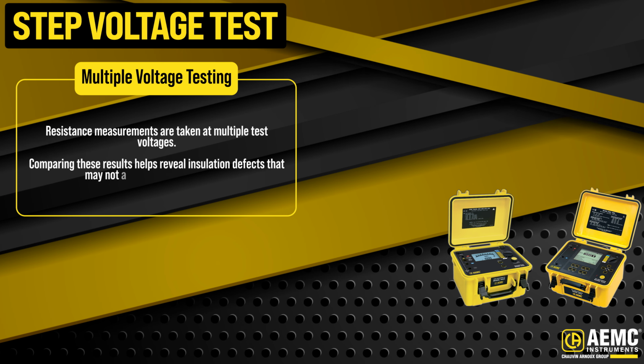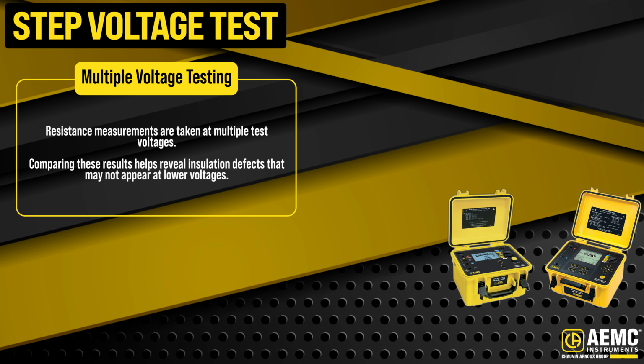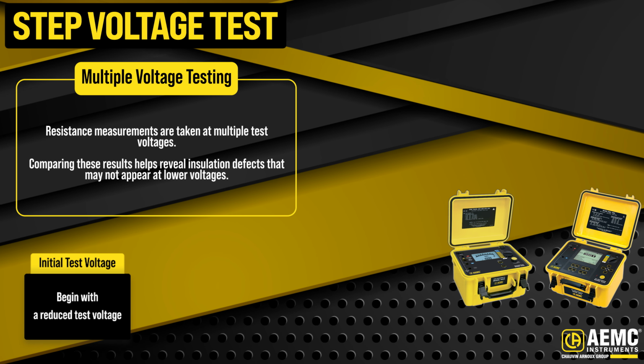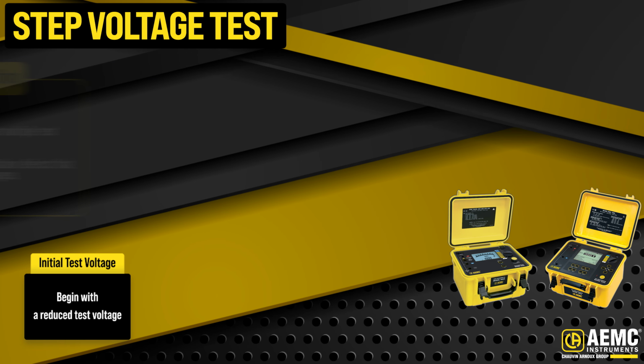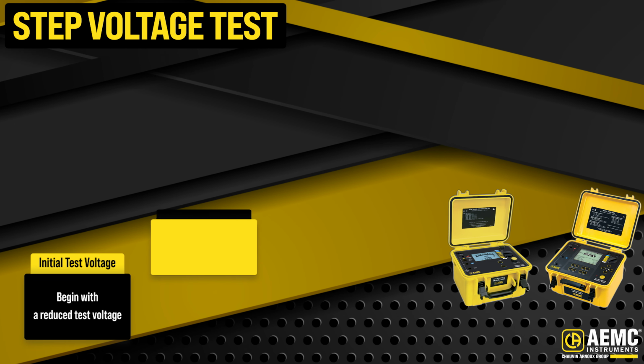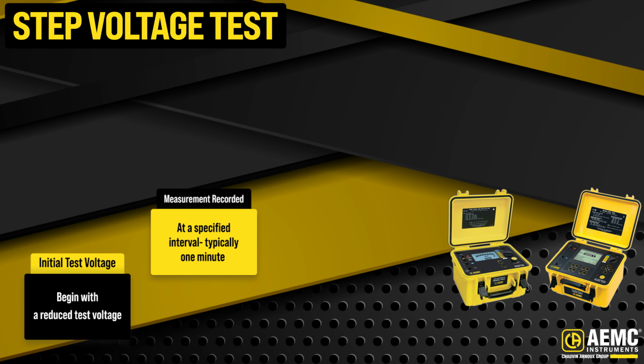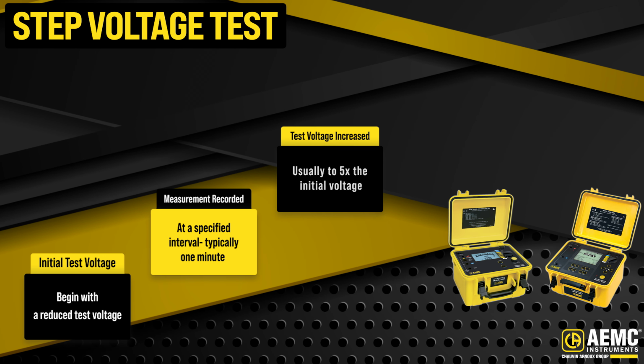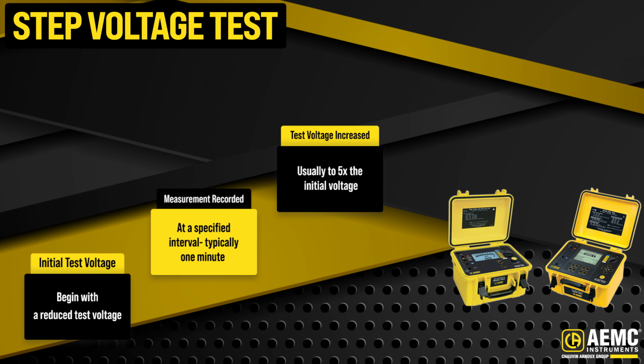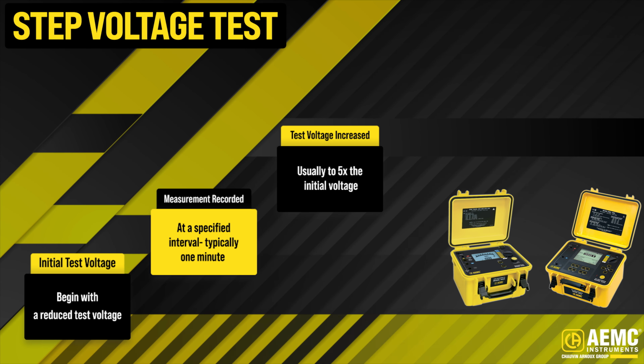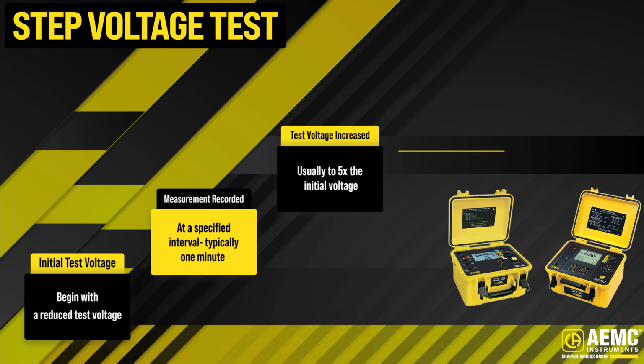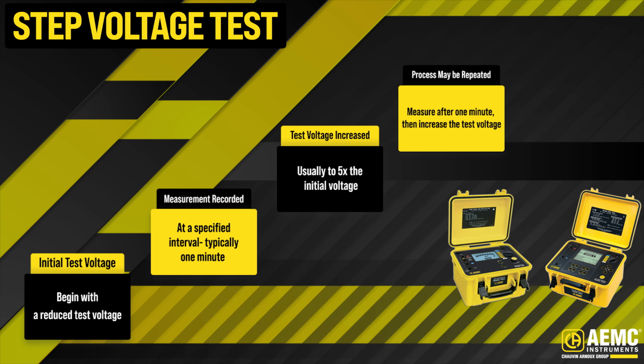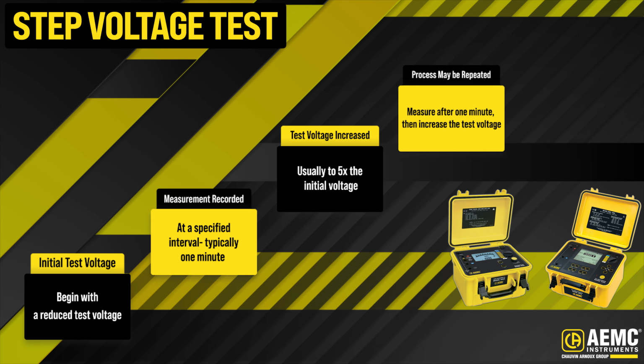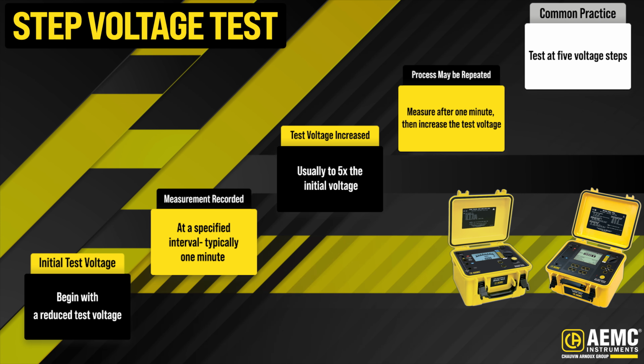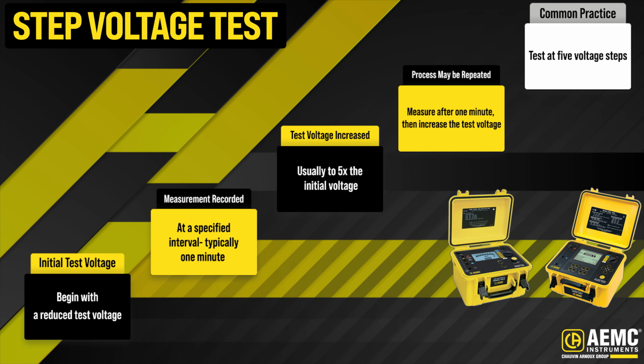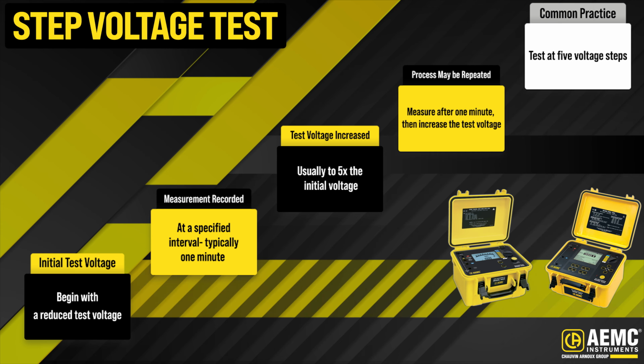This involves testing at 2 or more test voltages and comparing the results. The test begins at an initial test voltage. At a specified interval, typically 1 minute, a measurement is recorded, after which the test voltage is increased. This increase is usually to 5 times the initial voltage. This process may be repeated through several steps, with measurements taken after 1 minute and the test voltage increased. A common practice is to test at 5 voltage steps.